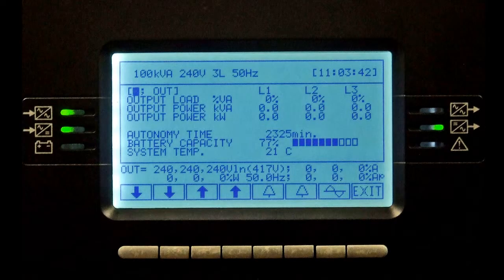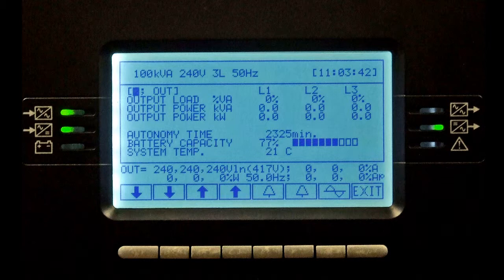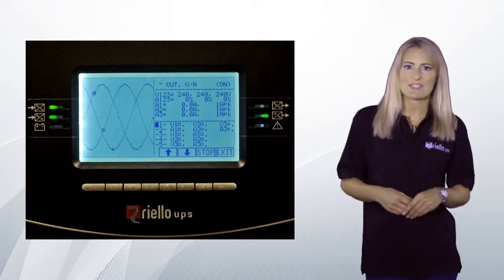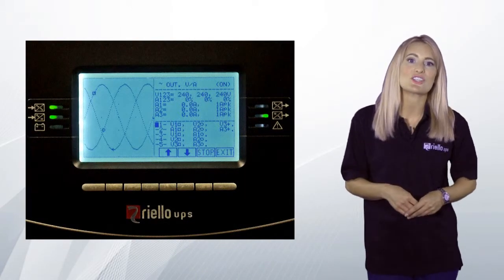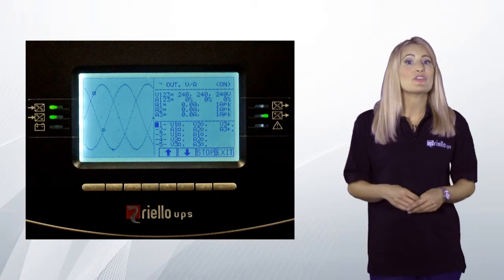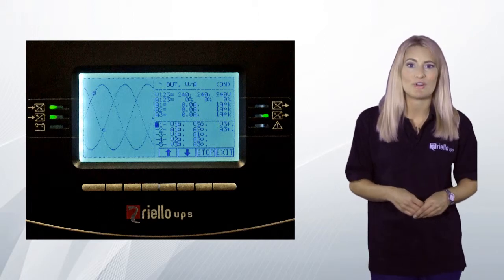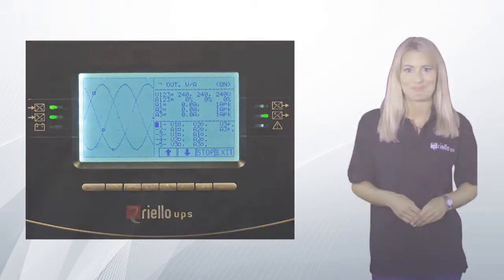From the previous screen, pressing button 1 or 2 again will display the power currently being drawn from the system, the current battery capacity and estimated autonomy, and the current system temperature. Finally, from the previous screen, press button 7 to enter the oscilloscope function, where you can view the UPS input and output voltage and current waveforms.